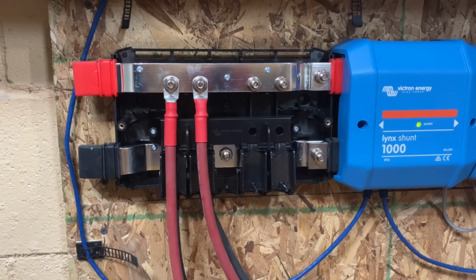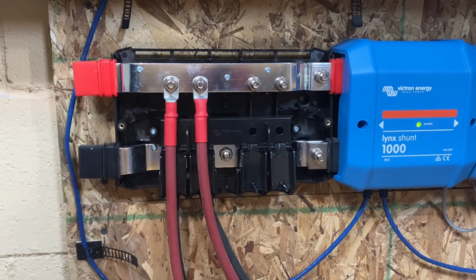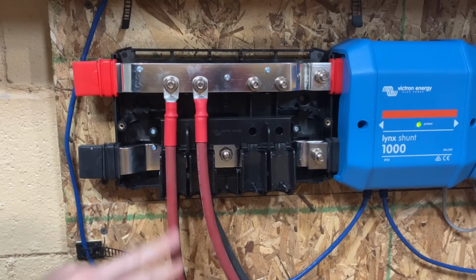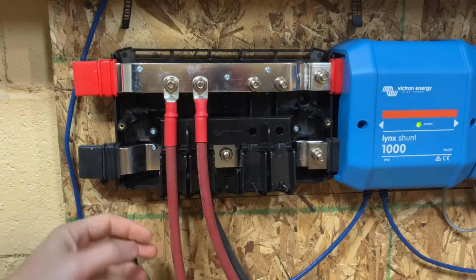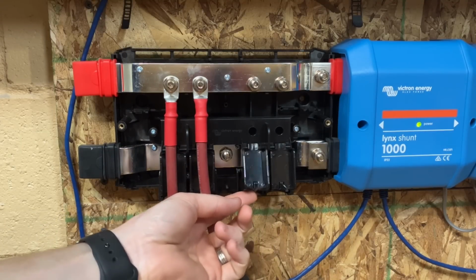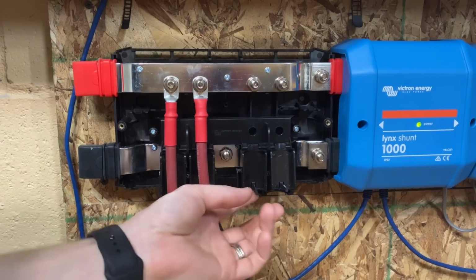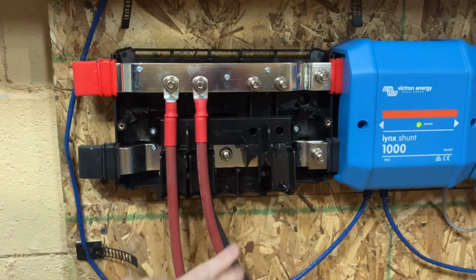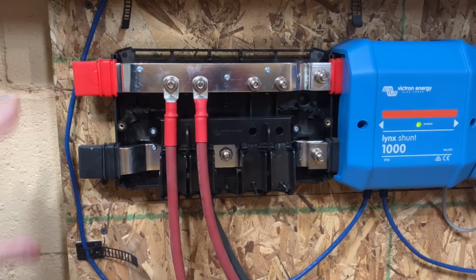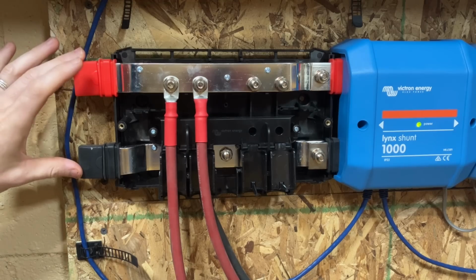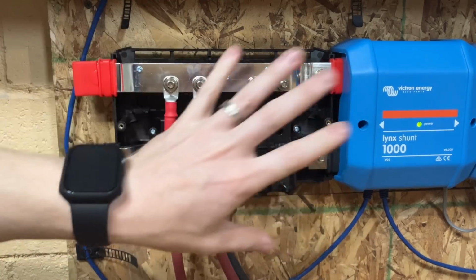With the cover off, looking at the Lynx Power In, it's a very simple system. Your positive and negative wires stack on top of each other, separated by dividers that give clean separation between the positive and negative bus bars. There's room for expansion on the side, and it's interconnected to the next component in the string.